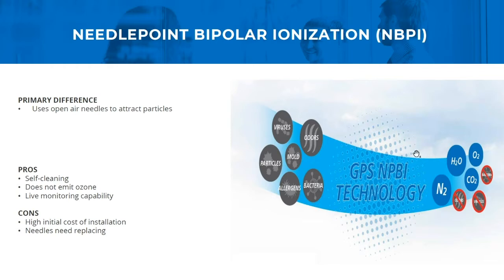Sure, definitely. So typically what happens when the ionization system is emitting ions is it sends out either a positive or a negative ion. Those ions then attach themselves to either a negative or a positive ion, rendering them harmless. So if you have a positive VOC ion, the needlepoint system will send a negative ion that will attach to it, and they'll essentially become harmless as they cancel each other when they're attracted to one another. So the system is very capable of producing good ions that will help clean the indoor air quality of your air handler. Excellent.